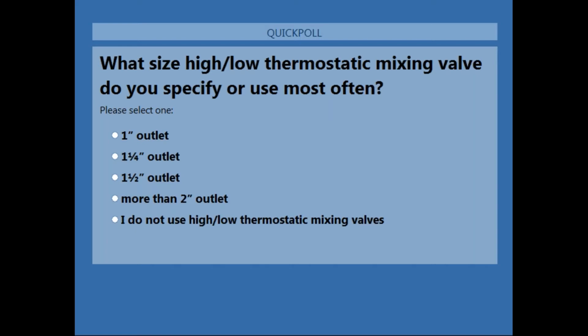And we see that again on radiant systems where they say, oh, I'll just put a 1-inch instead of a 1/2-inch valve, and it's the exact same valve, and then the CVs are probably going to be exactly the same. So it's not the pipe size that you're sizing your valves by; it's by the flow rate that you need to move through that valve to get them to perform properly.